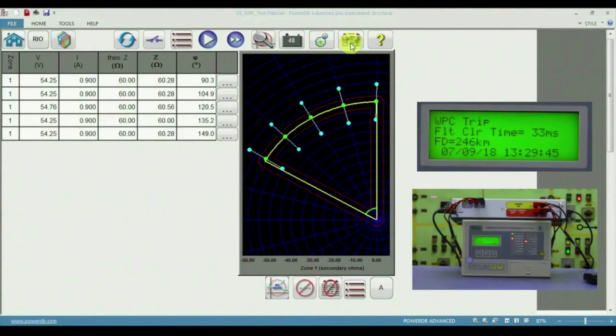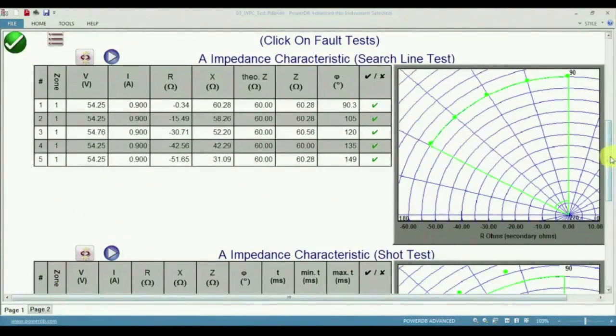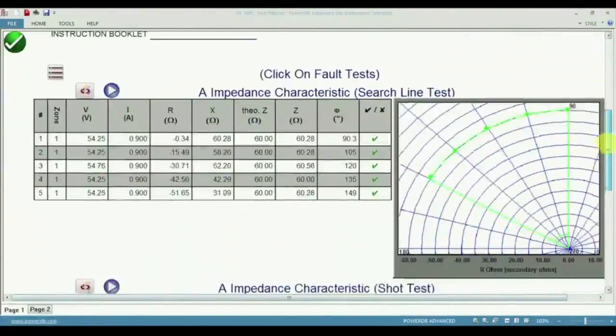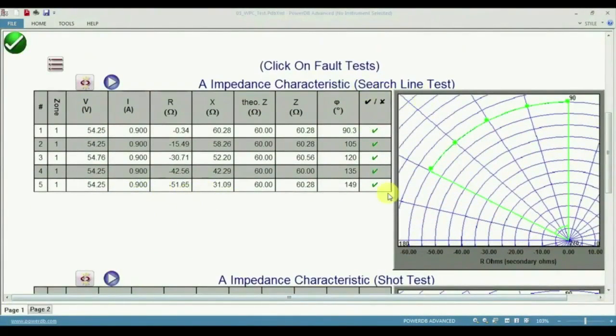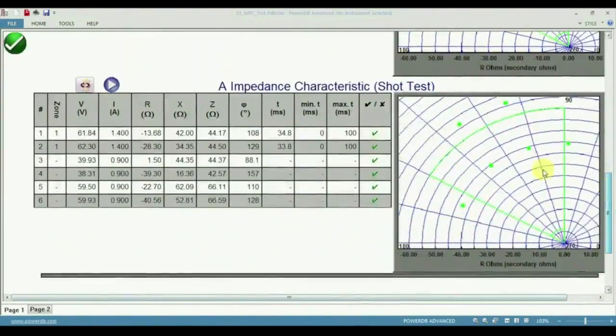So let's see the results by clicking here, saving impedance report. So it has 2 pages. Let's see page 1. This is the search test. You can see it has operated at 60 ohms, that is the outer boundary. And the next is the shot test. So you can see it has operated at 34 milliseconds. So you can also see the region of operation, the region of non-operation, along with the timing in a single test.